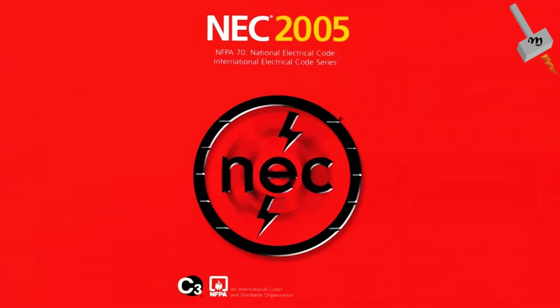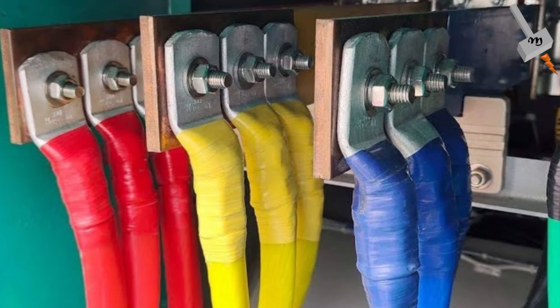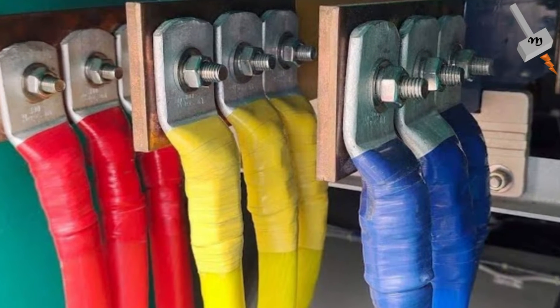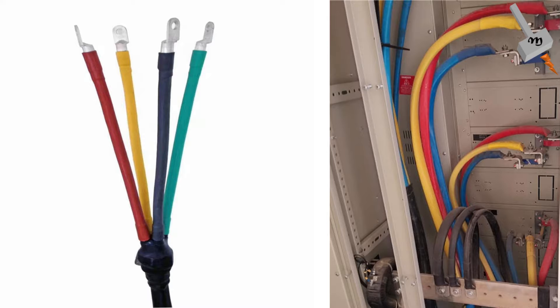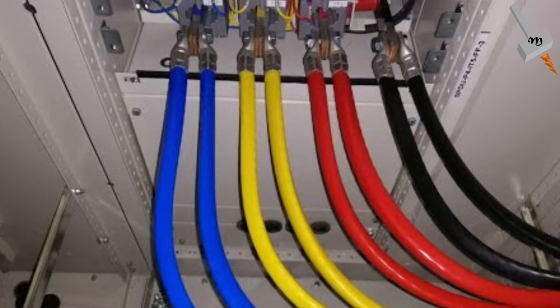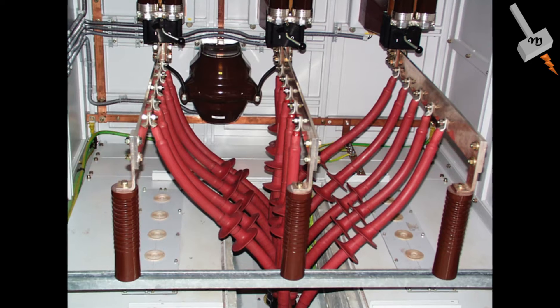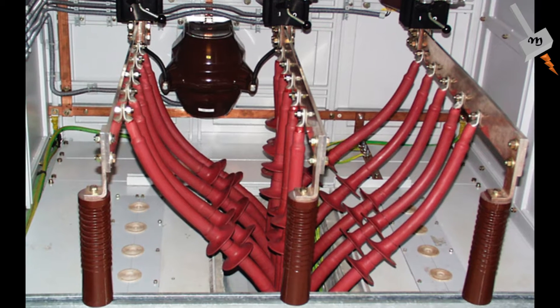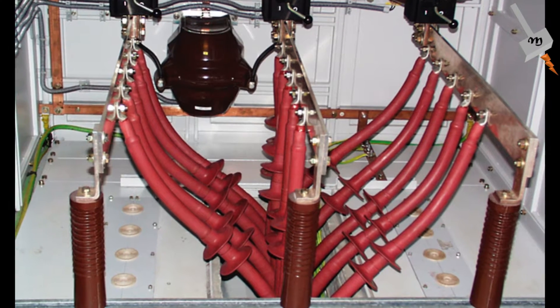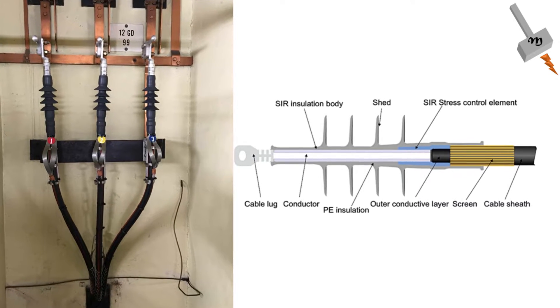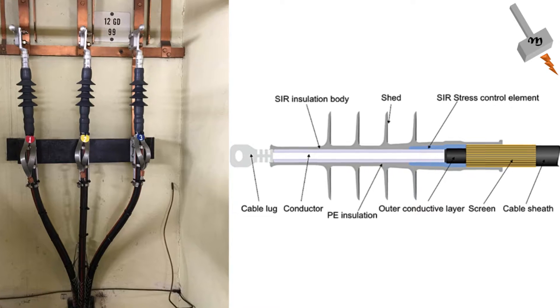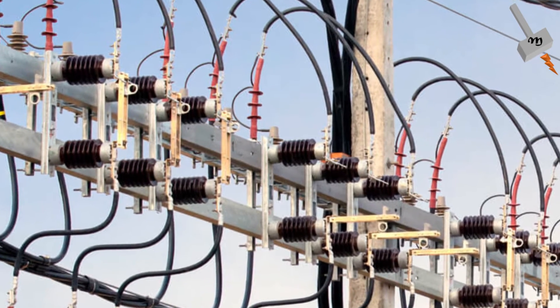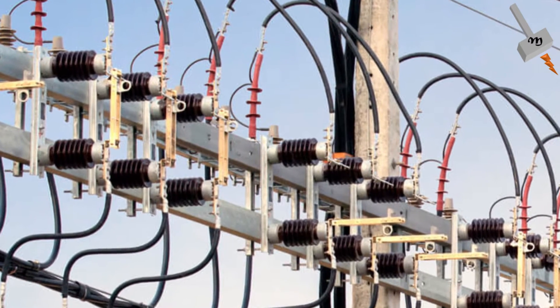The National Electrical Code standard only allows non-shielded cables for voltages less than 2000V, and with some listed exceptions, they can be used up to 2400V. Applications above 2400V should use shielded cables, which means cable terminations are required for all cables applied at voltages above 2000 or 2400V.